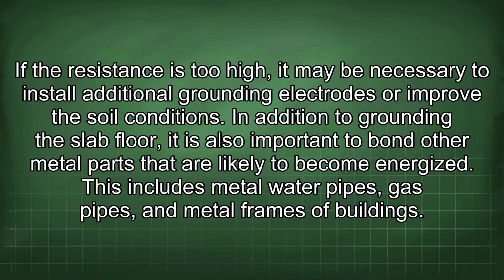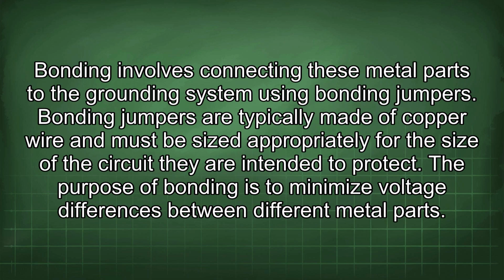In addition to grounding the slab floor, it is also important to bond other metal parts that are likely to become energized. This includes metal water pipes, gas pipes, and metal frames of buildings. Bonding involves connecting these metal parts to the grounding system using bonding jumpers. Bonding jumpers are typically made of copper wire and must be sized appropriately for the size of the circuit they are intended to protect. The purpose of bonding is to minimize voltage differences between different metal parts.